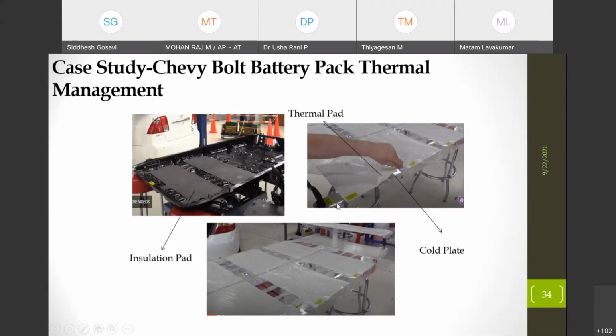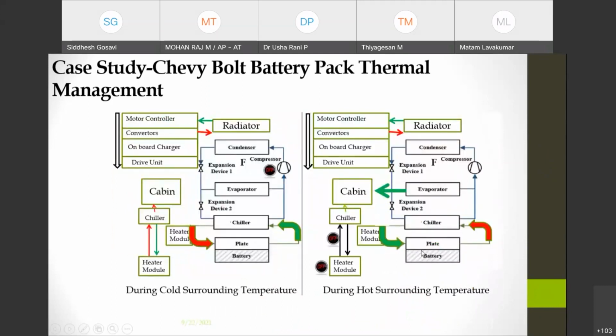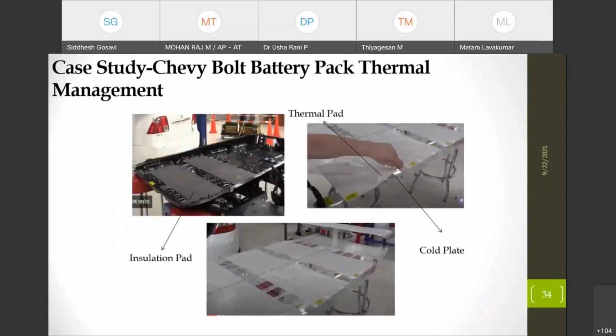As shown in the schematic, there should be perfect contact between the battery and the cold plate, but in reality there will be air pores regardless of manufacturing or assembly process. For that, we need a thermal interface material, like a clay type of material, a thermal pad, or a sticky glue, which fills all the air pores between the cold plate and the target medium, the cell.